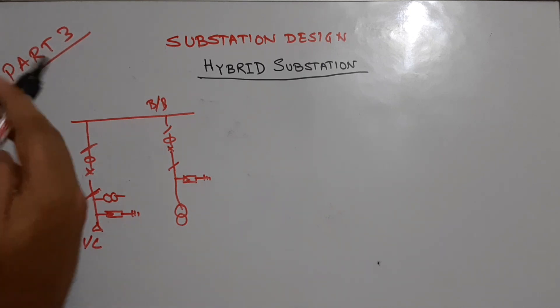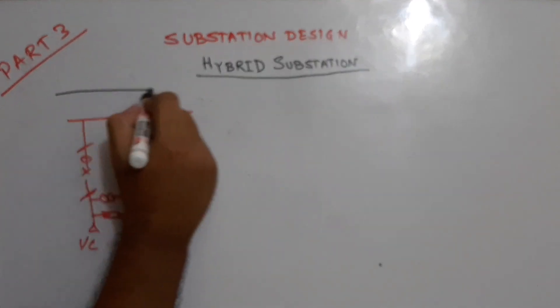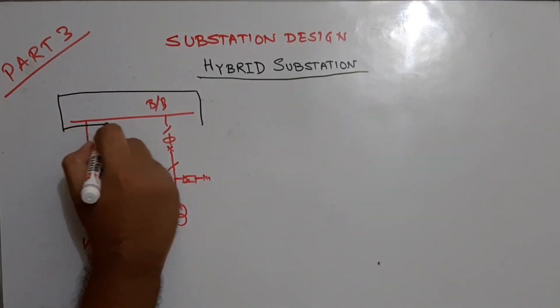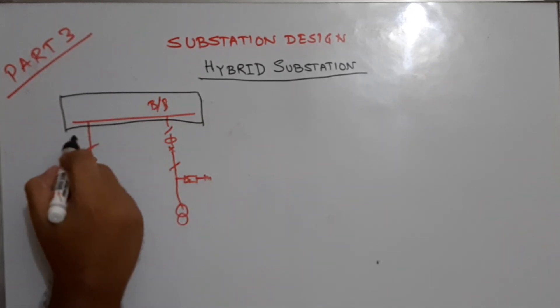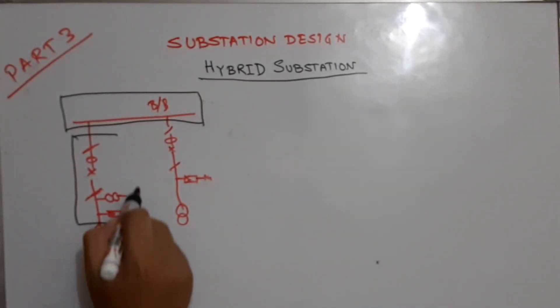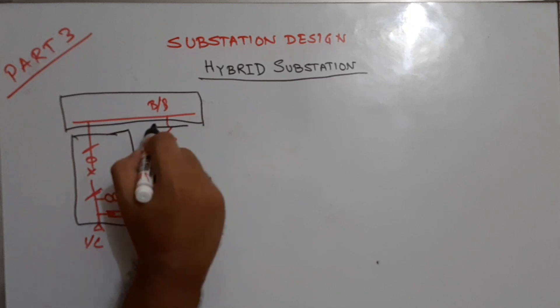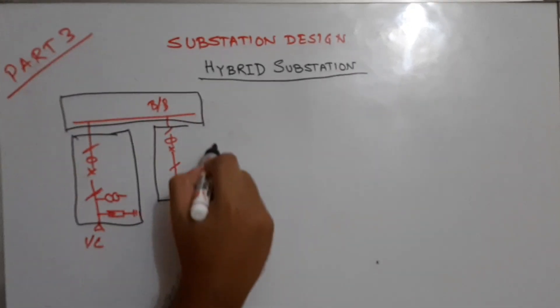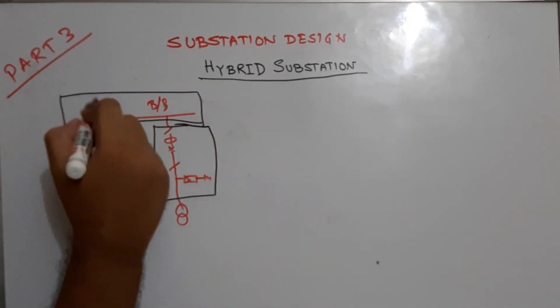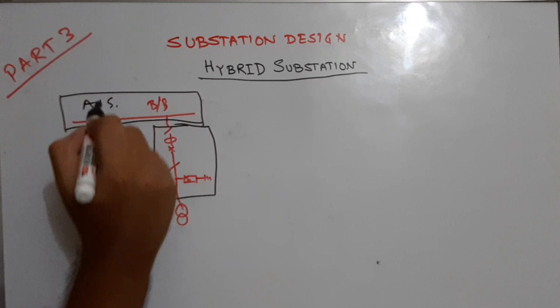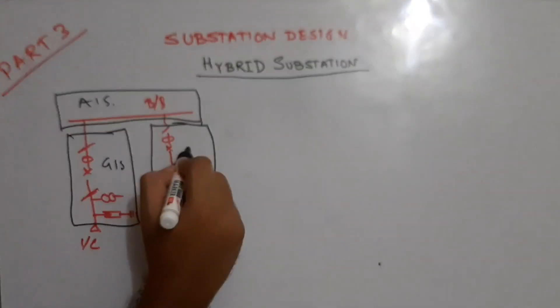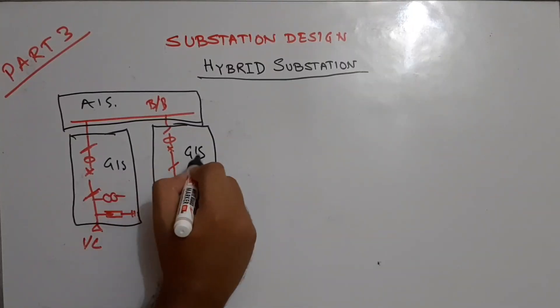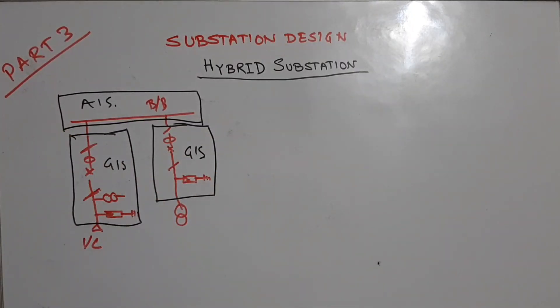For this to be a hybrid substation, the bus bar portion will be air insulated type — this is the AIS section. The switchgear portion will be gas insulated and enclosed — this is the GIS section. This is how the hybrid substation is formed.